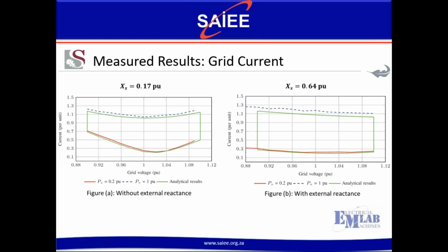This slide shows the measured results of grid current versus grid voltage and supply power for two test case scenarios, one where the inductances were added and one where they weren't added. The red portion of the curves indicate where the supply power was kept constant at 0.2 per unit, the dashed blue indicates where the supply power was kept constant at 1 per unit, and the green indicates the analytical results. As can be seen, a good agreement between the measured and analytical results was obtained.